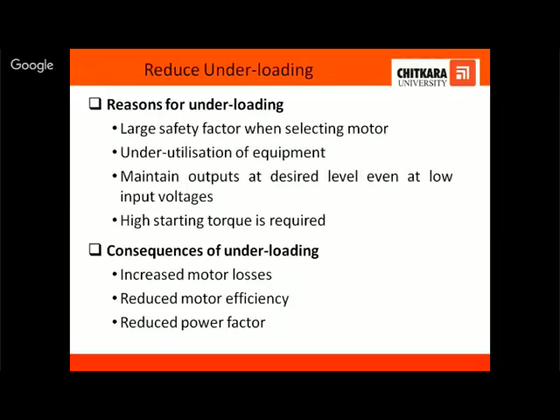low. Or sometimes we have used the motor for a particular process, but that equipment itself is underutilized, so it is not fully utilized and the motor load is less. Then sometimes, when we have to buy a new motor, the designer thinks that there may be fluctuations in the voltage, and sometimes the voltage level goes down. He wants the output of the motor to remain constant, so he goes for an oversized motor, so that even if the voltage is low, the power output remains the same. Then sometimes we need a high starting torque, so for high starting torque, we choose a motor of a higher size.